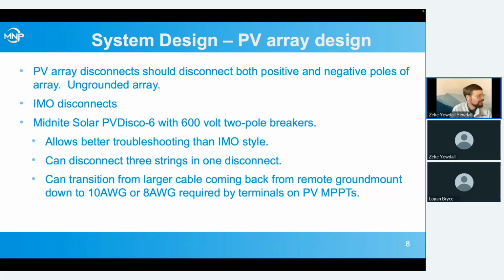PV array disconnects. Obviously, we've got the one built onto the side of the inverter, but often you want an external one where the PV circuits enter the building. Especially if you've got a remote ground mount, you might want to have a disconnect at the ground mount before it goes underground, a couple hundred feet to the house.